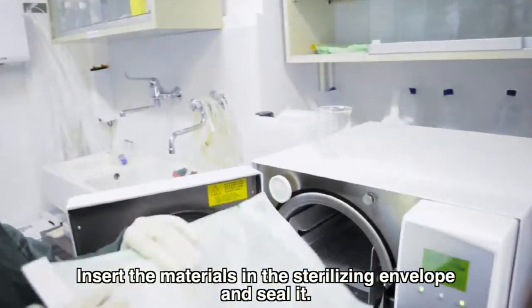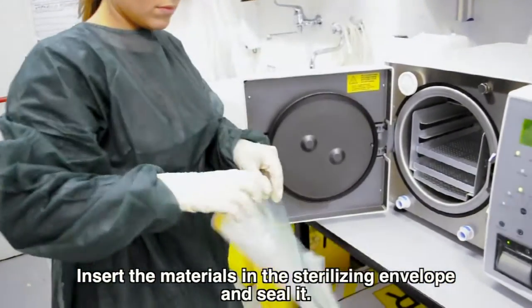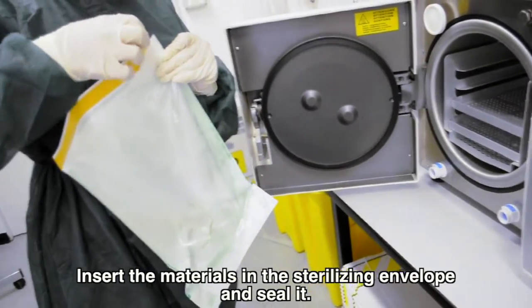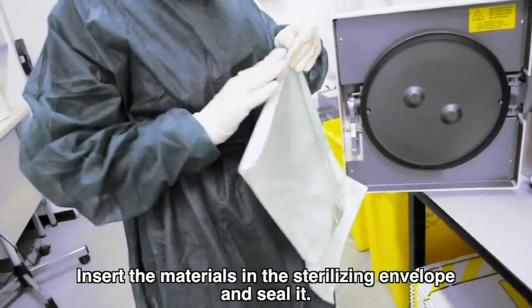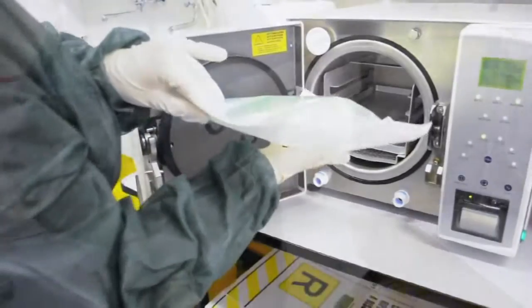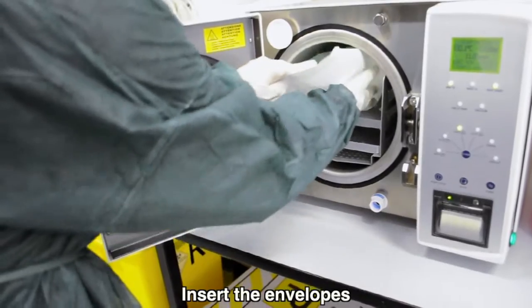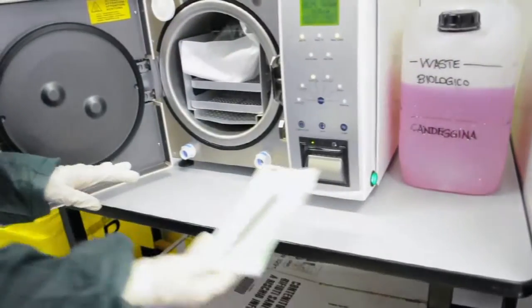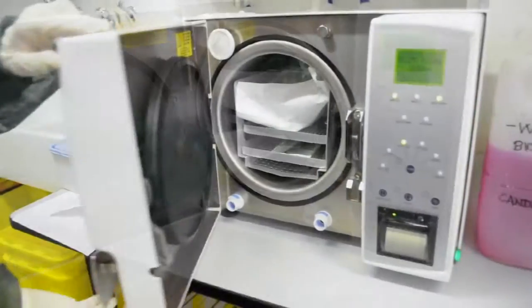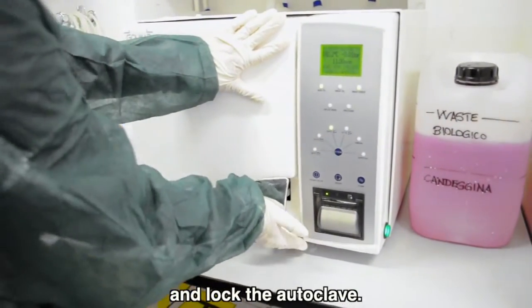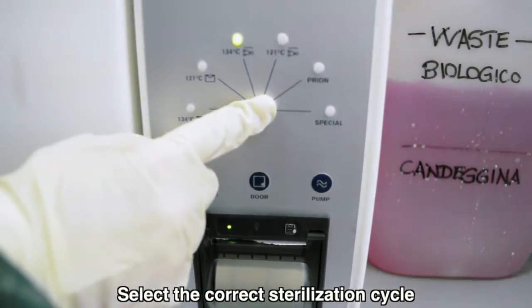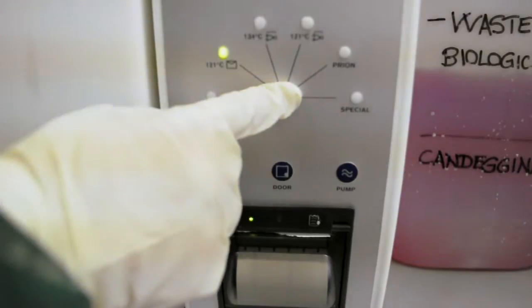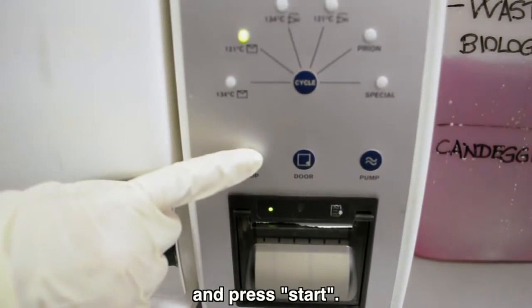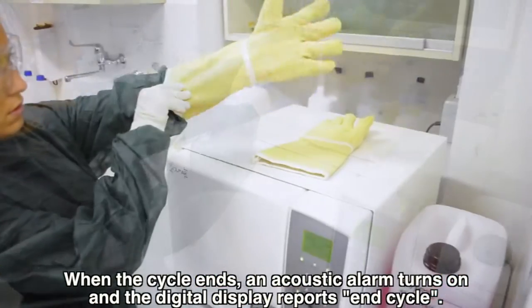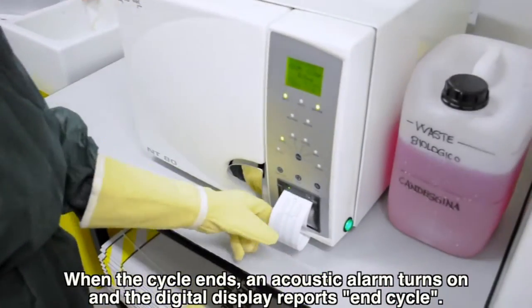Insert the materials in the sterilizing envelope and seal it. Insert the envelopes. And lock the autoclave. Select the correct sterilization cycle and press Start. When the cycle ends, an acoustic alarm turns on and the digital display reports End Cycle.